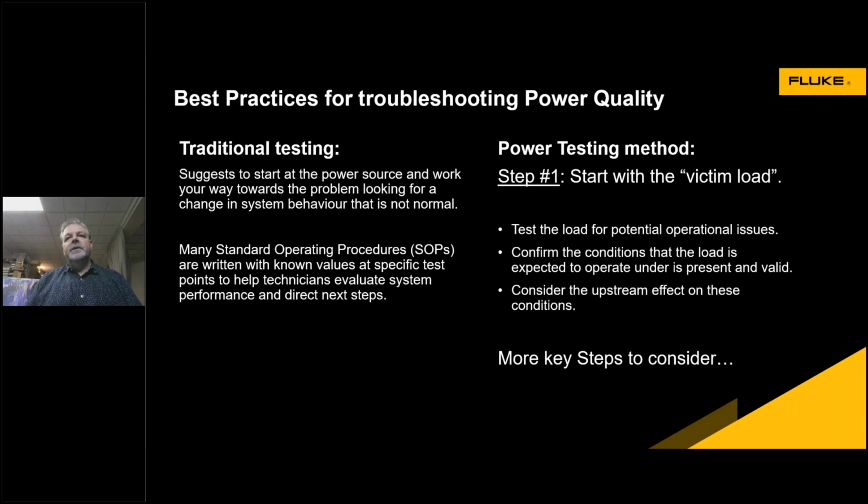Confirm the conditions that the load is expected to operate under, and that it's getting the voltage and current available to it in the right shape, the right conditions to be able to operate. And then if it isn't, consider anything upstream from that as to what could be the problem. And there's more steps to consider as a part of this whole discussion.